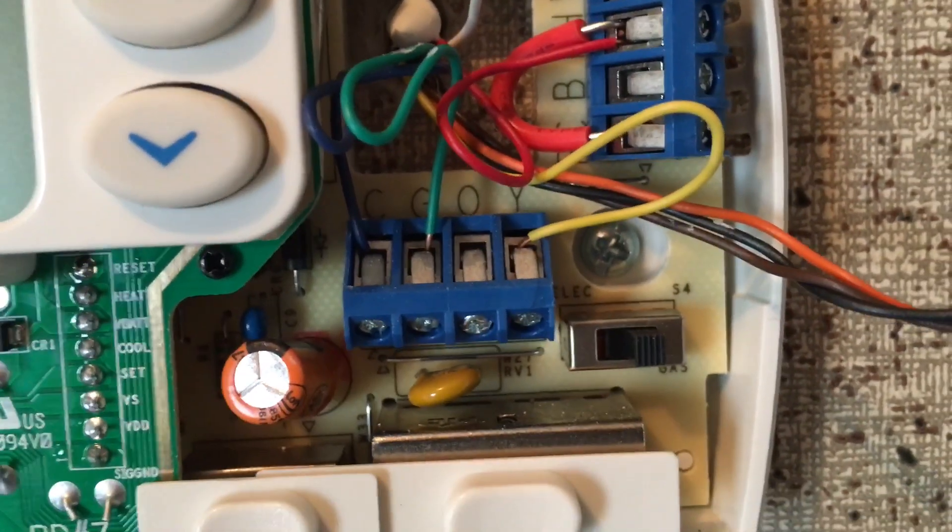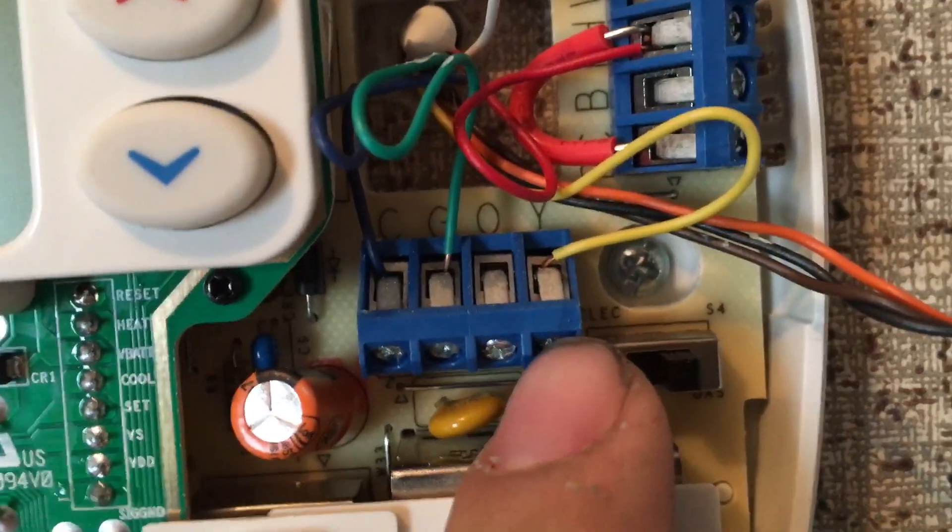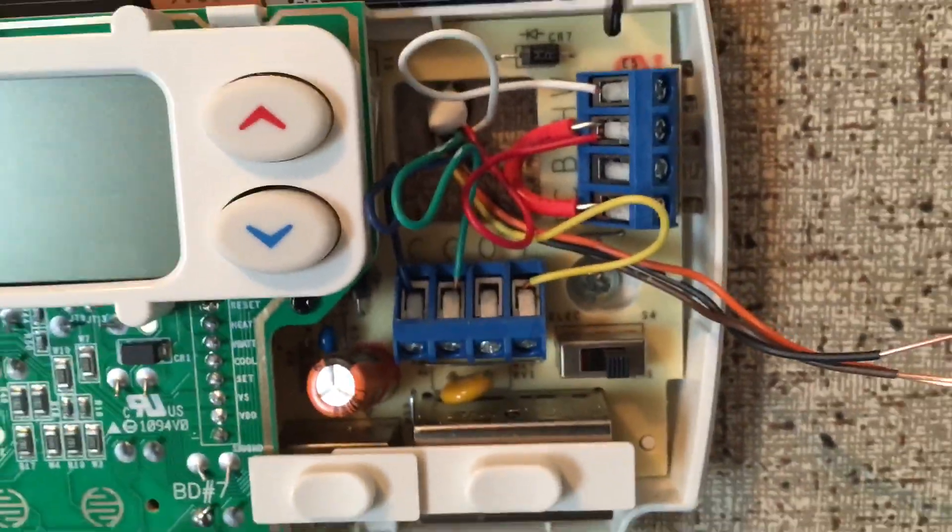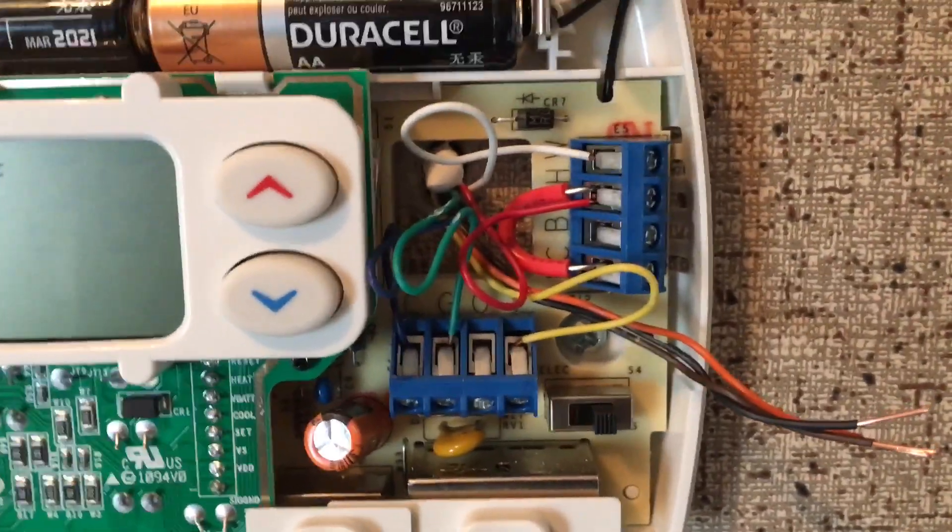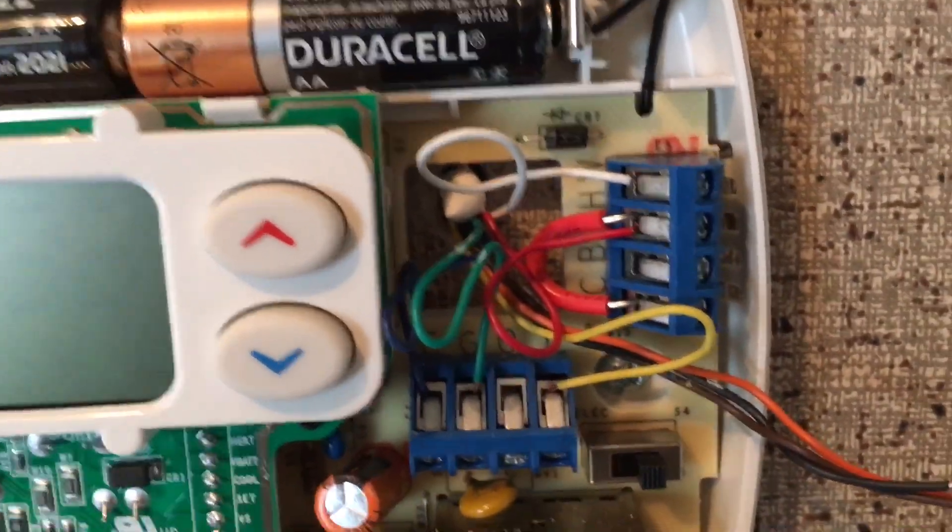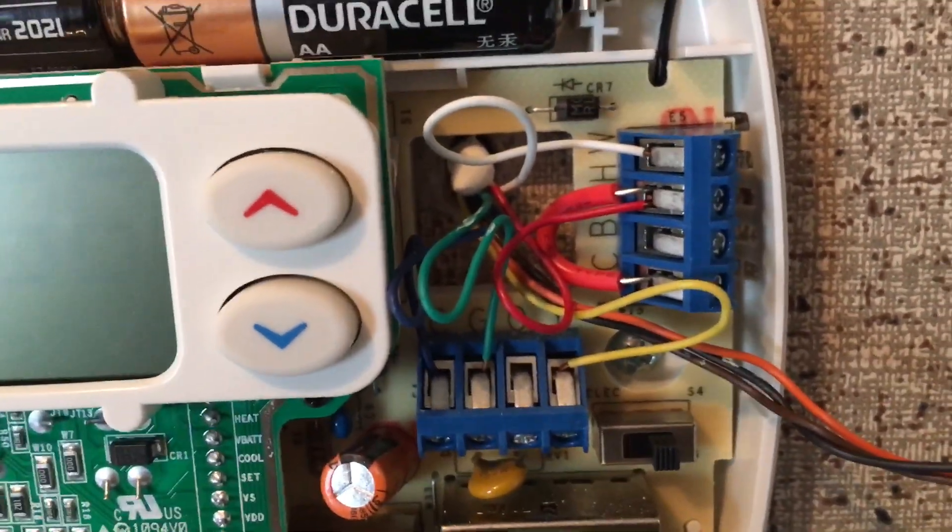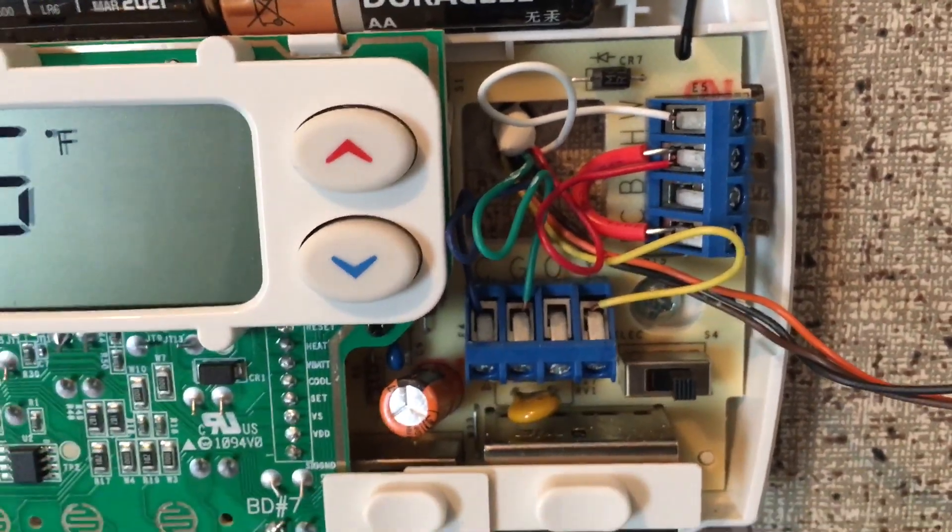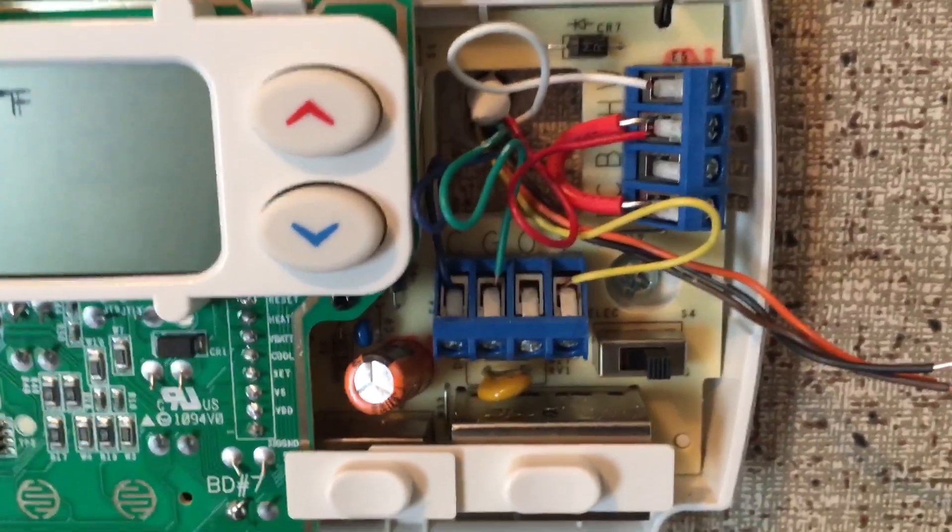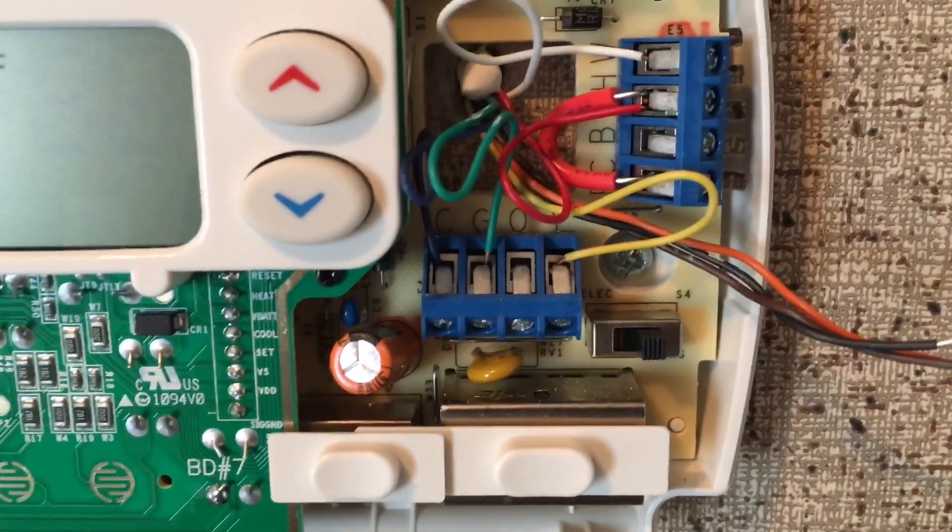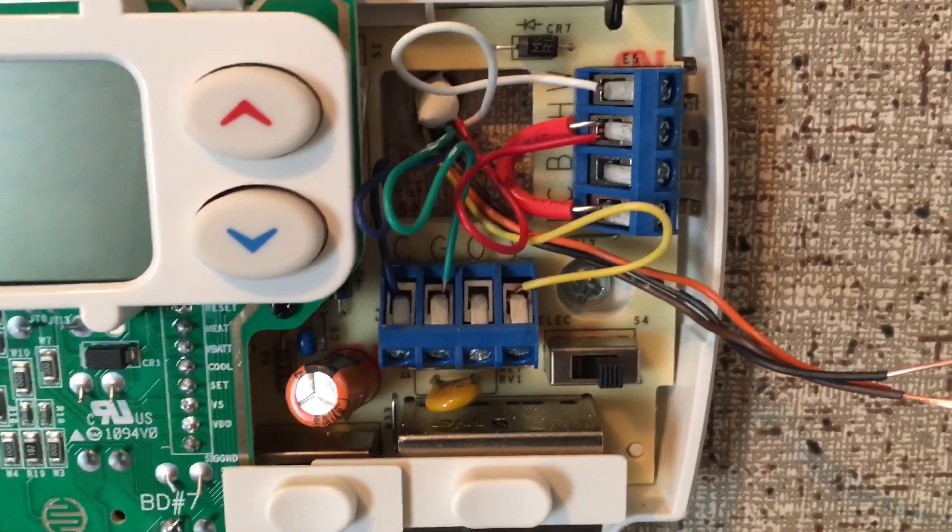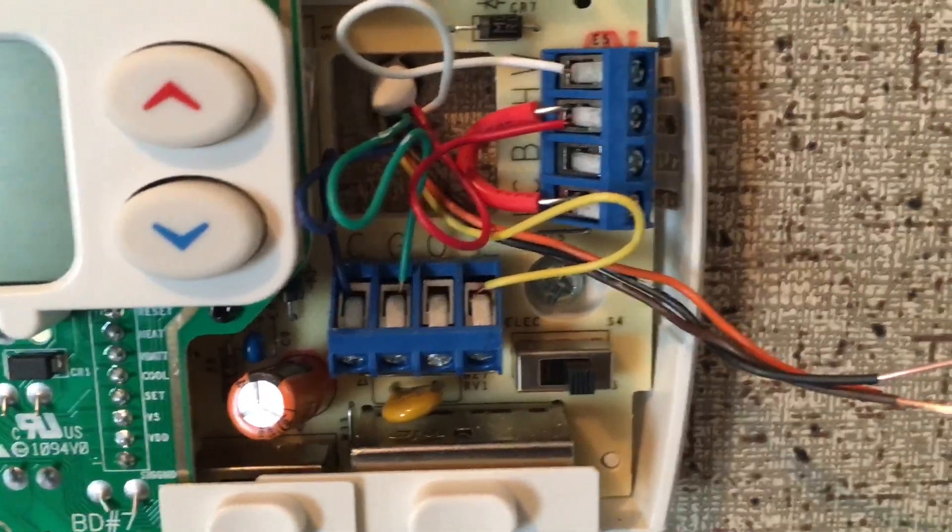Okay, real quick: the white wire is what commonly controls your heat. The red wire is going to be half of your 24 volts, which is what's going to actually send the signal. The green wire controls your fan. The yellow wire actually turns your air conditioner on and off.